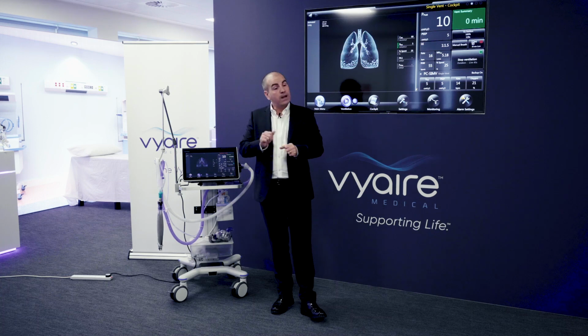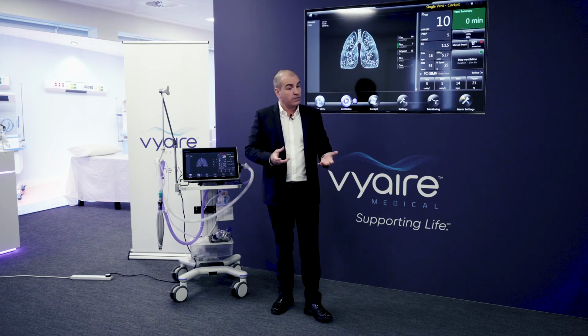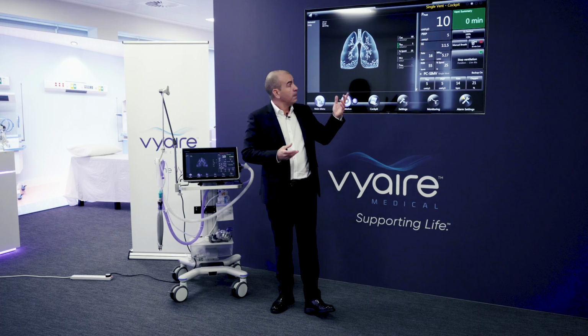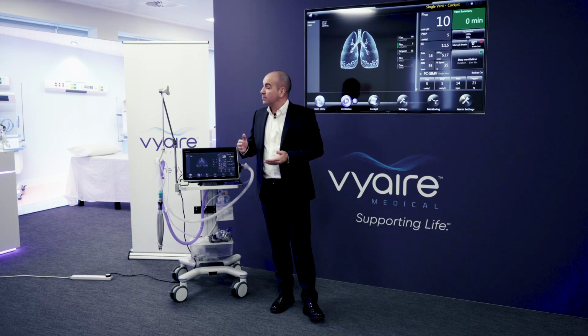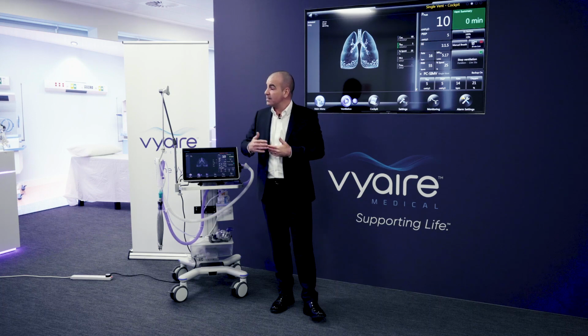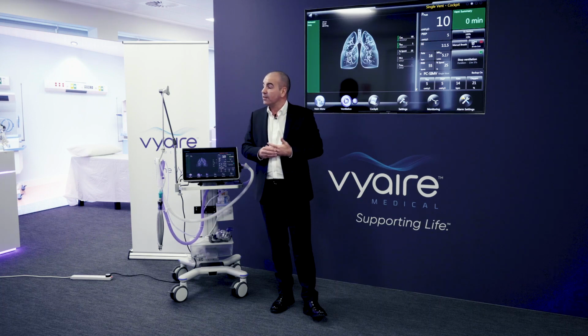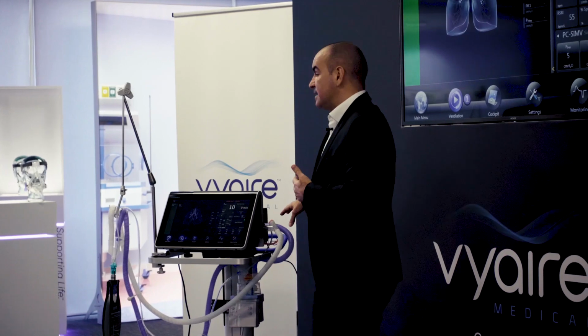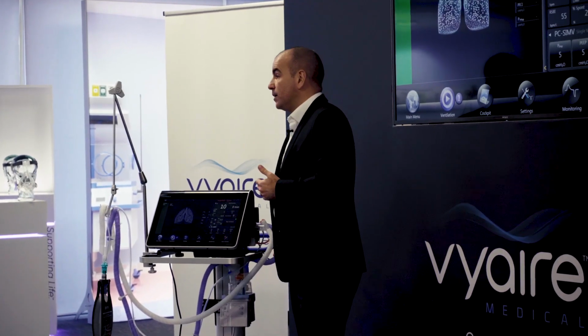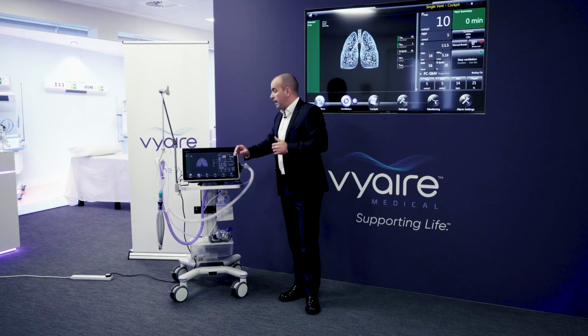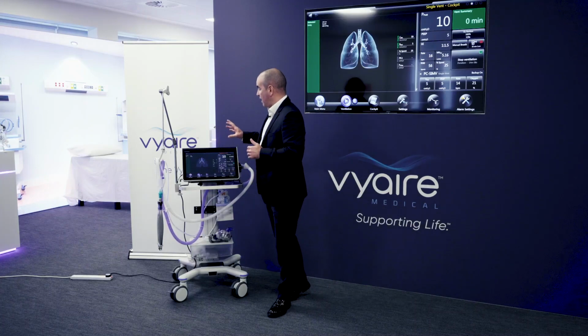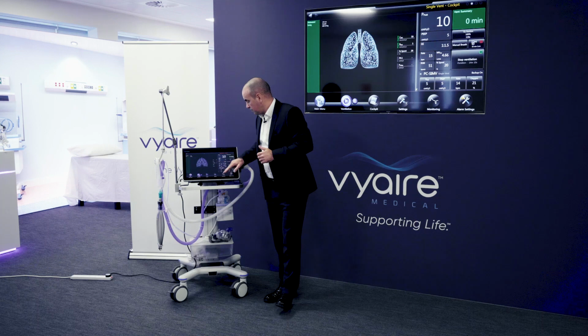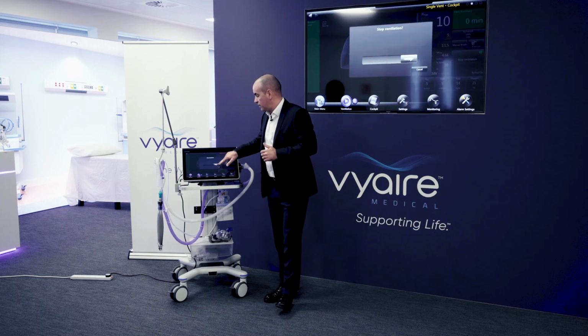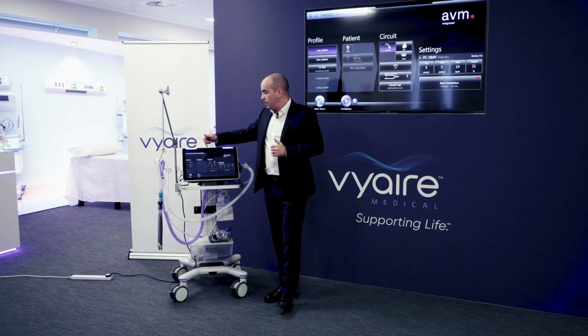Now, sometimes the nurses break the circuit and they might need to suction the patient. It gives you a 3-minute grace period there so that it doesn't go back to zero, so the patient's not going to be sat there wide awake and having to potentially stay on the device longer than necessary. The device itself, we can connect our heated circuits, our AirLife circuits.